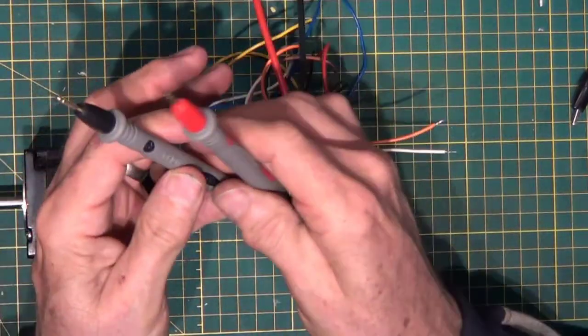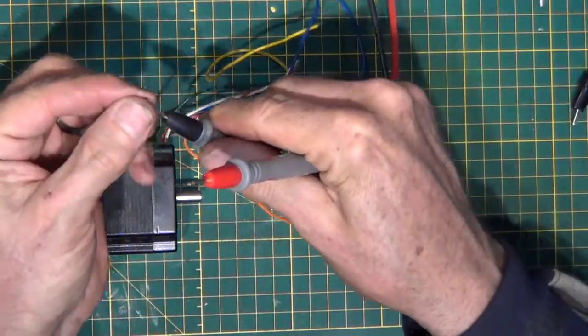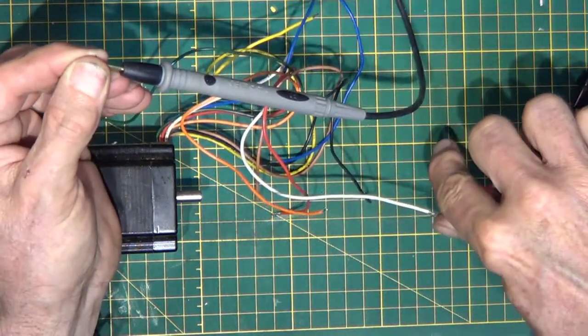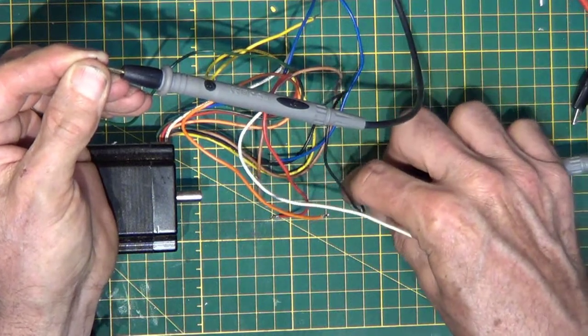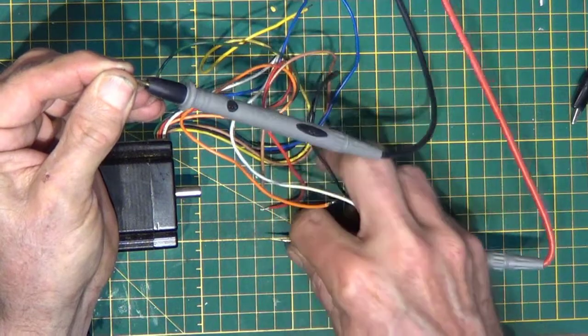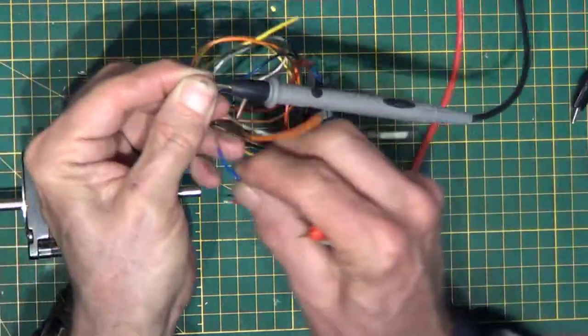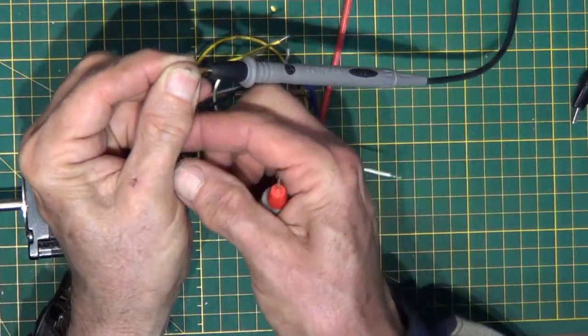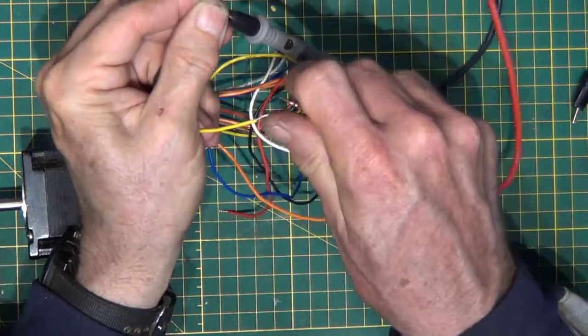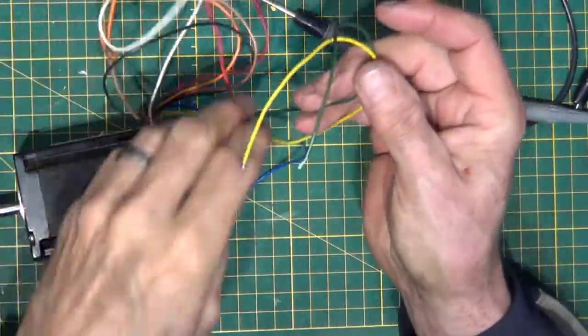I have a digital multimeter set for continuity. I'm going to go through individual wires and try and find a pair. I'm working on green to orange, nothing. Green to white, nothing. Green to black, nothing. Green to red, green to brown, nothing. Green to blue, nothing. Green to yellow. So green and yellow are one coil in this motor.